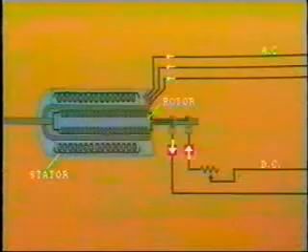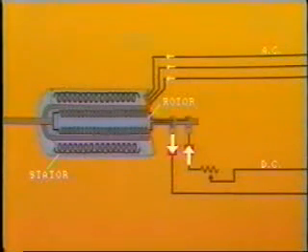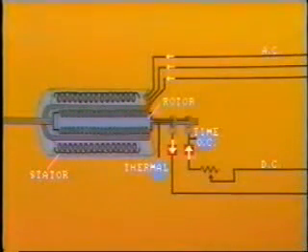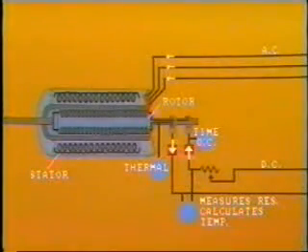Generally speaking, protection for the synchronous motor is similar to that for the induction motor, but with the addition of a few special relays. One particular condition to protect against is that of overexcitation of the rotor. Conceivably, automatic power factor control or voltage control could result in excessive DC current flowing through the rotor field windings and so lead to overheating of the rotor. Protection is provided by either a time overcurrent relay or a thermal bimetallic relay connected into the field winding circuit. Another, more direct method measures the resistance of the field winding, and from this calculates the temperature. These relays are wired to sound an alarm, or perhaps in an unattended station to trip the unit.